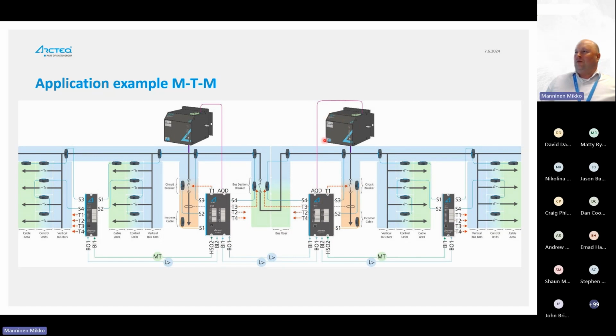And why do we have 2? Because of the tie breaker. If the tie breaker is open, we have a safe, less than 4 millisecond system on the left side and also on the right side. So this is an example. If there's a flash anywhere in the board, the relay will measure the current, one of the relays will monitor the light, and then the quencher is closed and the breakers are opened.